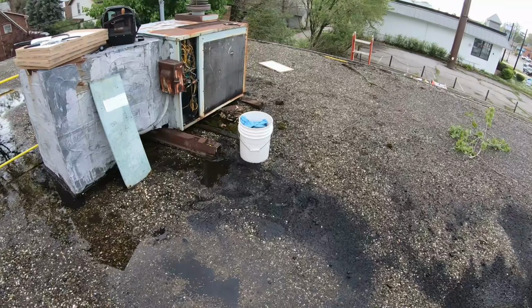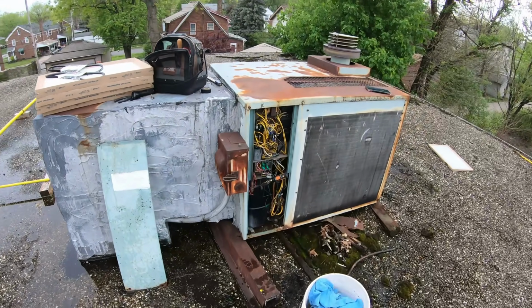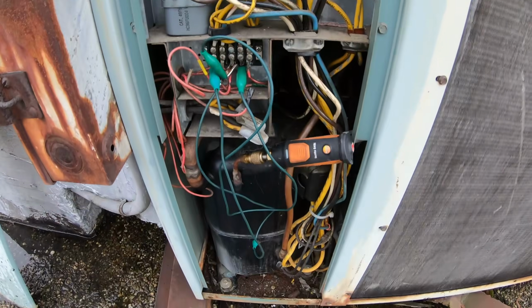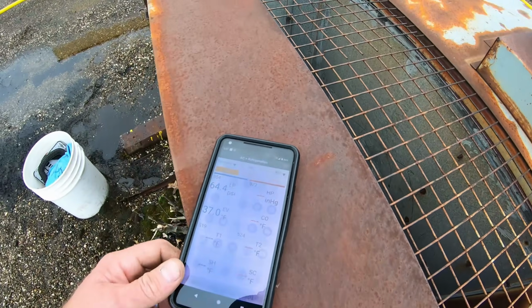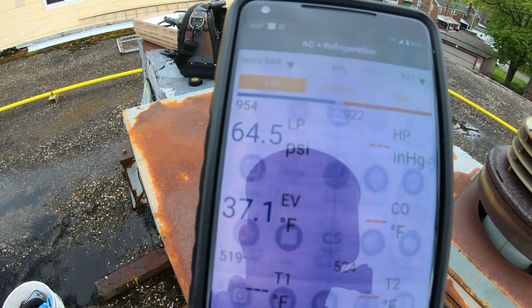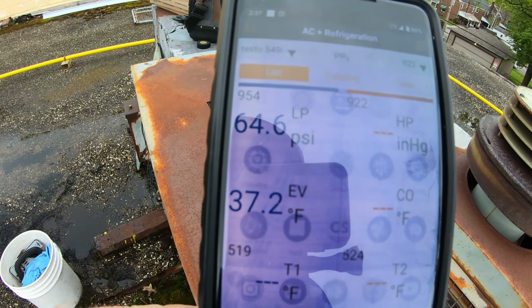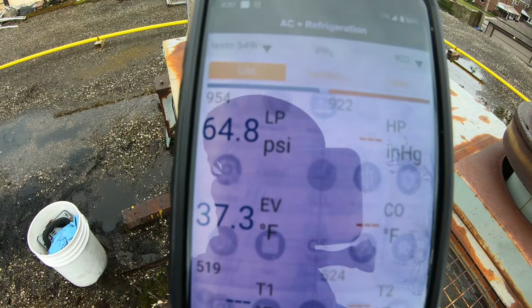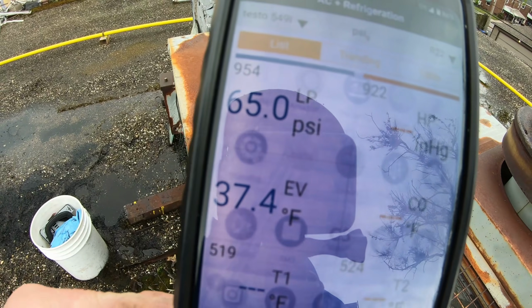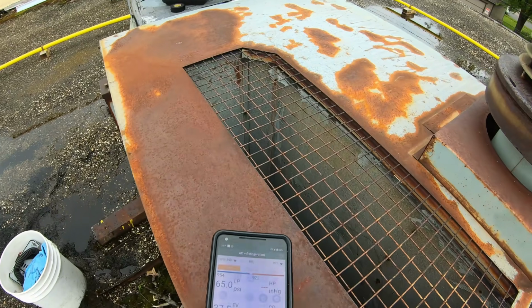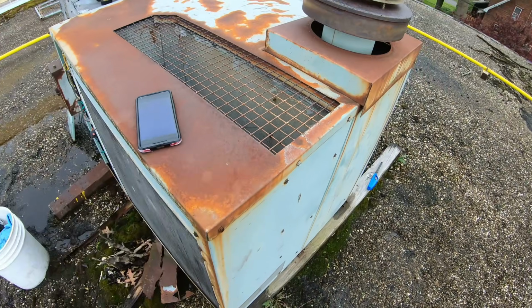Geez, I got hiccups, I got sneezes. Running about 64 pounds of suction pressure. I don't even see a liquid line port on this, so she ain't freezing, she's blowing, she got a new filter.